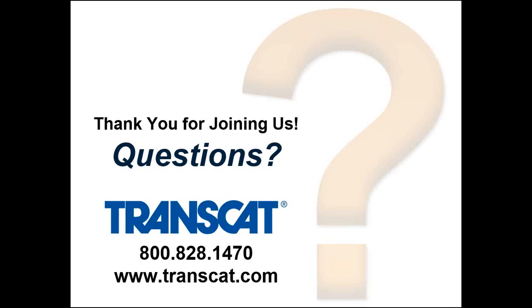Okay, thank you, Howard. And then it looks like one final question. If calibrations should be performed with a 4-to-1 rule for the standards to UUT, what is the typical rule of thumb for the manufacturer's floor process specification and test equipment they use to take these manufacturing process measurements? Again, I've seen 4-to-1 used in those applications.